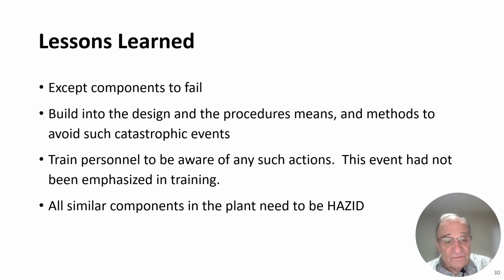When the site was visited after the event, there were turbine blades everywhere, sticking out of the insulation and other components in the plant. The shaft of the turbine, which was about 4 inches in diameter, was blown out of the turbine casing and bent like a pretzel. It was a catastrophic type of accident, and fortunately, the 6 employees who ducked for cover, none of them were injured other than having quite a fright.